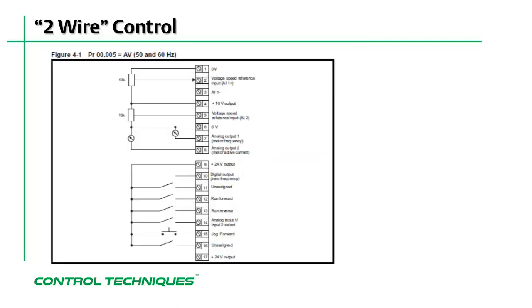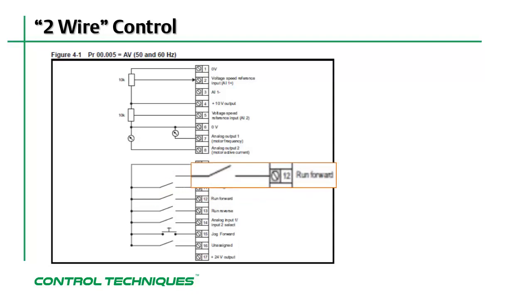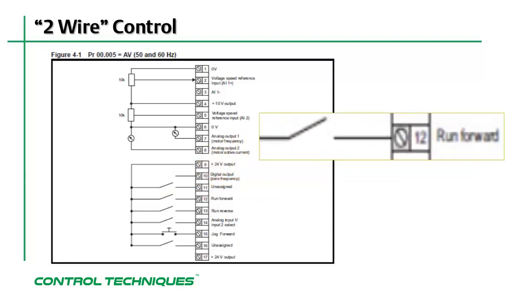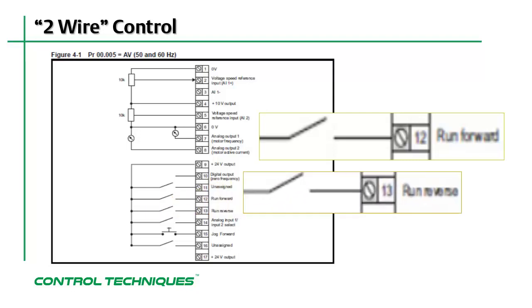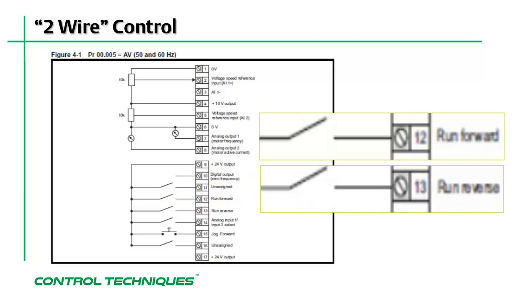With menu 0, parameter 5 at its default setting of AV, the drive sequencer is configured to be in what is referred to as two-wire control mode. It's called two-wire control because there is one wire to run the motor forward and a second wire to run the motor in reverse.